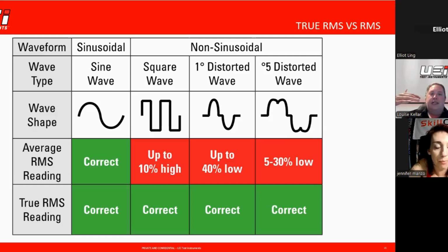That was the standard technology in a lot of clamp meters, and there are still many clamp meters out there that are average sensing. Because it didn't know when it was hitting the peaks and valleys, a lot of technicians will tell you they like an analog gauge. It was literally because they could see if there were any distortions—it may not have been the actual numbers they were looking at, but the fact that they could see distortion on that meter helped diagnose if something was going awry.